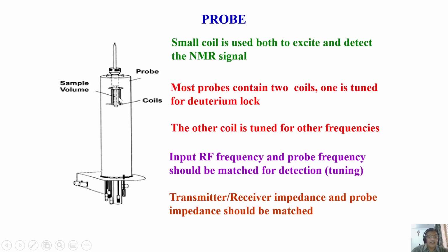They should perfectly agree. If there is no impedance matching, then all this power you apply through the radio frequency pulse through this coil will not go to the sample. Some of it gets reflected. It is called reflected power. So the matching is an important thing.